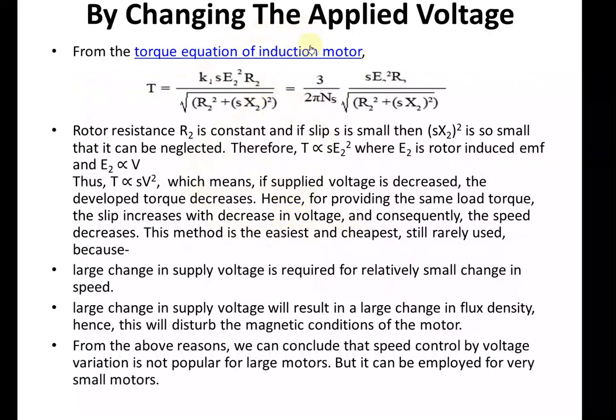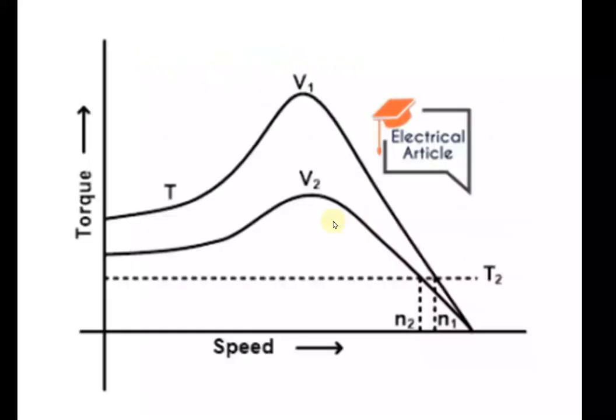The disadvantage of the changing applied voltage method is that a large change in supply voltage is required. Suppose you want to control a speed of 20 to 30 rpm — hundreds of volts need to be decreased. So a large change in supply voltage is required for a relatively very small change in speed. This large change will cause a large change in flux density, which will disturb the magnetic conditions of the induction motor. Because of such reasons, the changing applied voltage method is not so convenient.